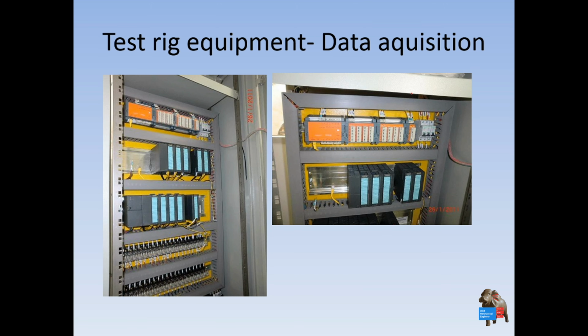And for data acquisition, you may need a PLC system and data acquisition systems. Let's say you want a test rig with a controllable system. For example, you control the opening of the valve to reach a specific flow capacity from the computer. So you don't need to climb up or control manually, and it depends on your needs actually. But mostly pump manufacturers make it more automatic to ensure that testing is done in a more efficient and effective way. So they invest some amount of money in the test rig.